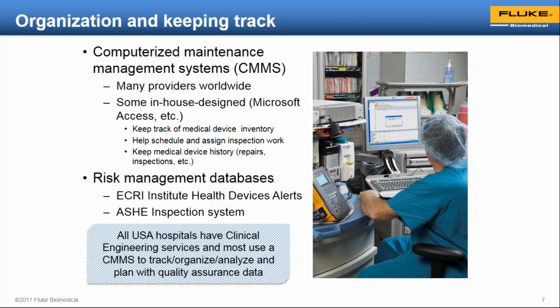How do we keep track? So most of you will have a computerized maintenance management system that is a database where you keep track of the inventory of medical devices. You also get your work assignments from there, and you track, or should track, any recalls or any voluntary corrective actions on the part of the manufacturers of those medical devices, and any service reports from outside service providers. So that would include the service engineers from the medical device manufacturer itself, or any third-party engineer that's coming in to do work on a medical device or help you get through your preventive maintenance schedule.